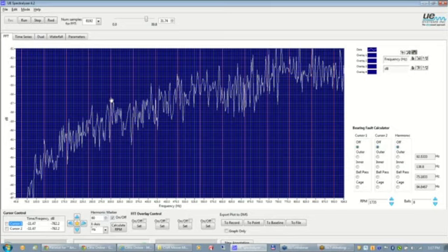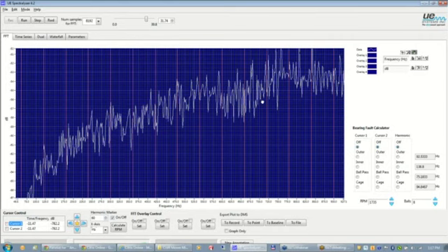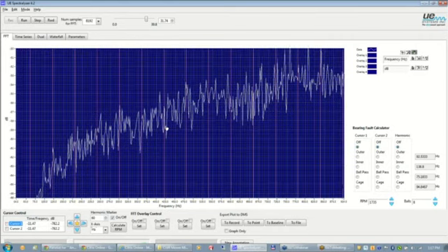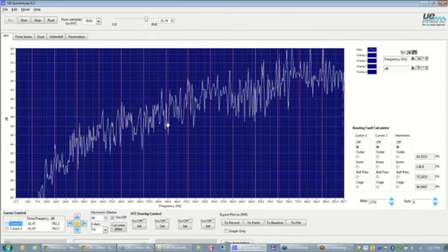And right here at 300, you can see it beginning to peak and hit right on that frequency. And then further out on the spectrum, nothing really hits directly on the harmonic. So the way I would characterize this is we have a fault frequency in the very beginning part of the spectrum on 60 Hertz harmonics.